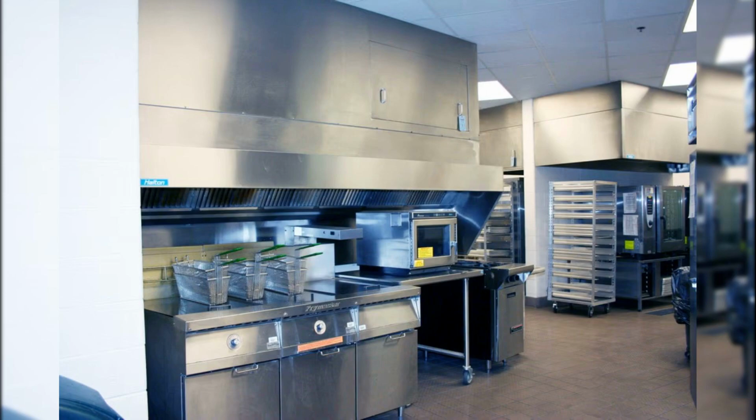Section 6.2.22 Kitchen ventilation. Applies to full kitchens, warming pantries, and cafetoriums. Two design approaches. Case 1. Combined cafeteria, kitchen unit, cheaper, preferred for small jobs. Case 2. Separate cafeteria unit plus dedicated kitchen makeup unit, higher efficiency for large projects.